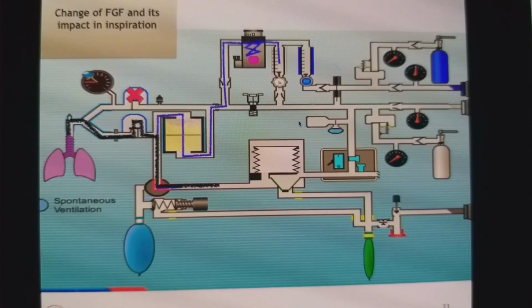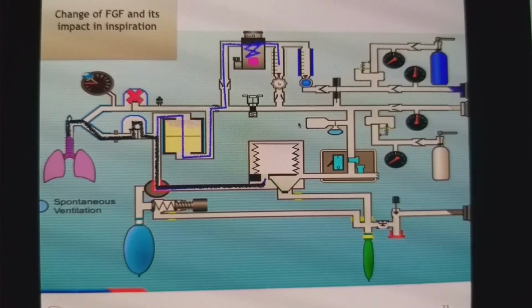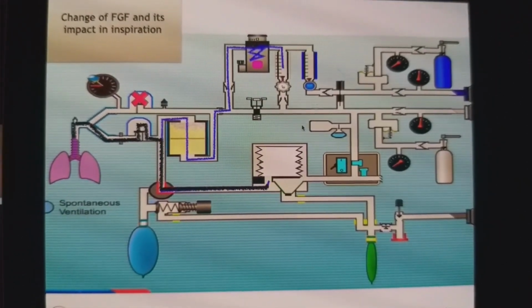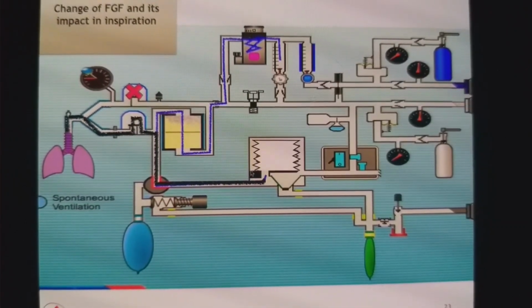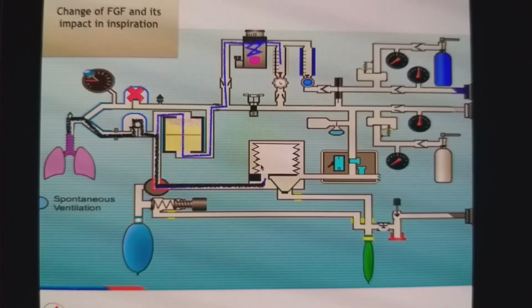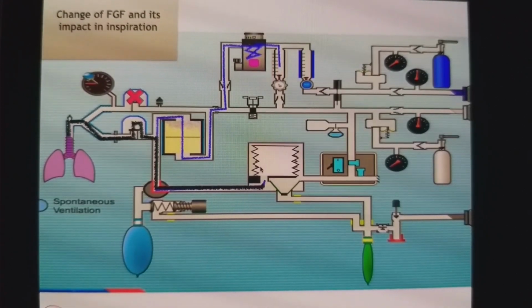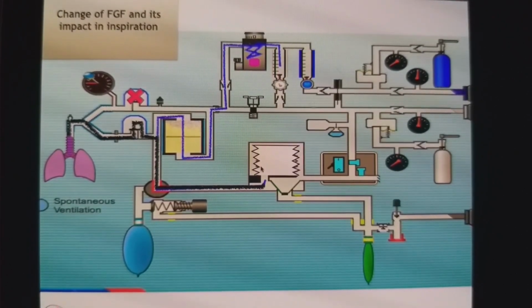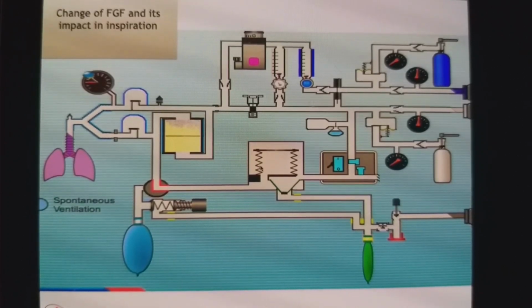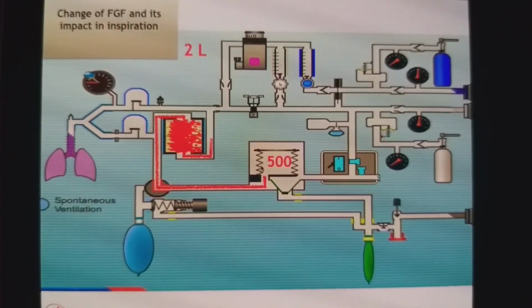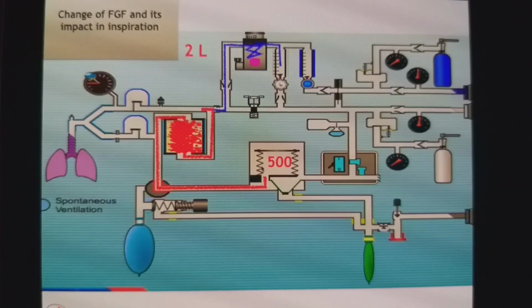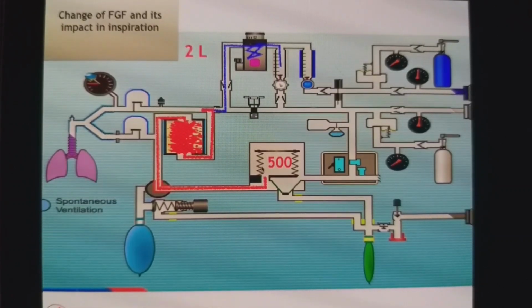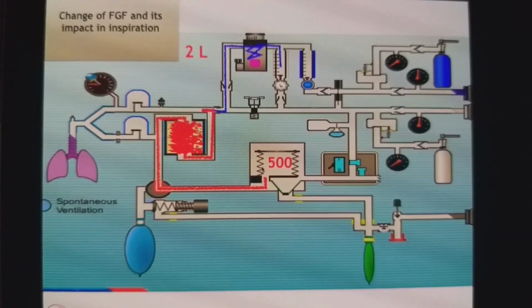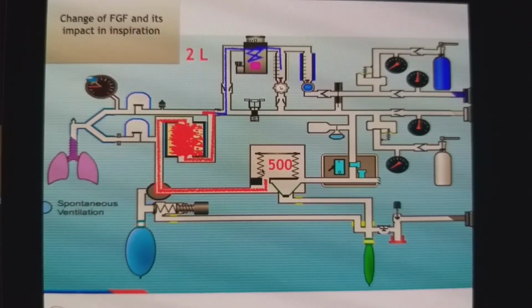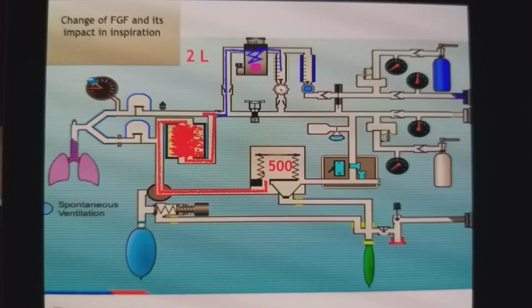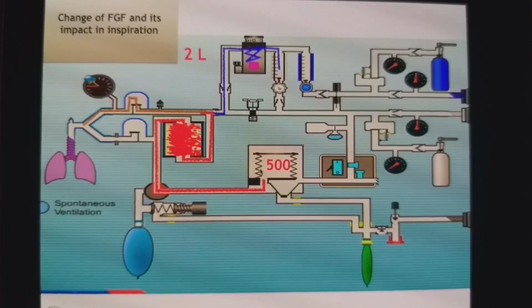If you decide to use a ventilator, then during expiration, in many anesthesia machines all gas will go to the bellows. At the same time, fresh gas flow will also go to the bellows. When the ventilator's bellows are squeezed for the tidal volume, let's say we have set a 500 ml tidal volume, 500 ml of gas from the bellows will go to the inspiratory line. Simultaneously, flow from the flow meter will also go to the inspiratory line. Together, it will be delivered to the patient.